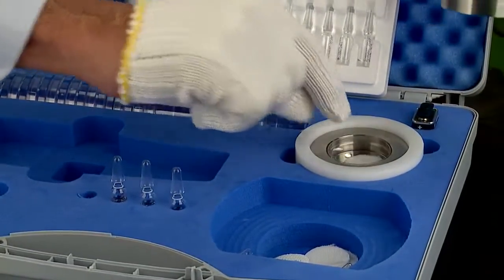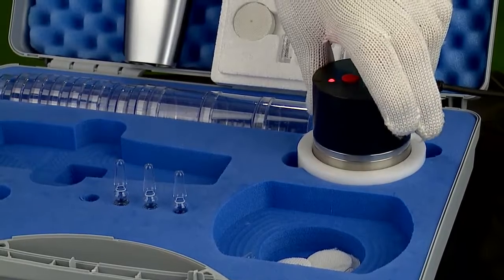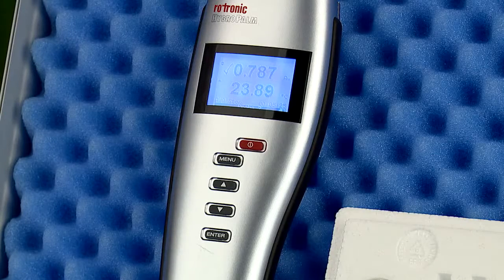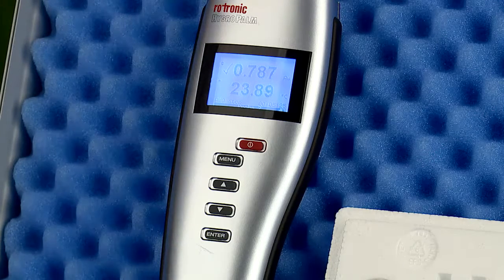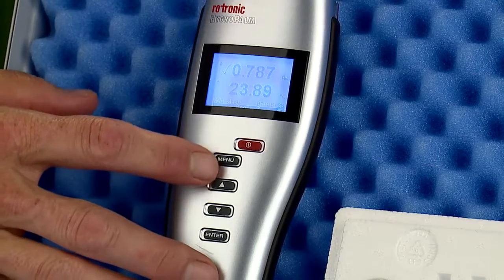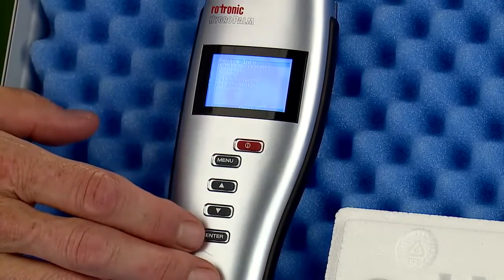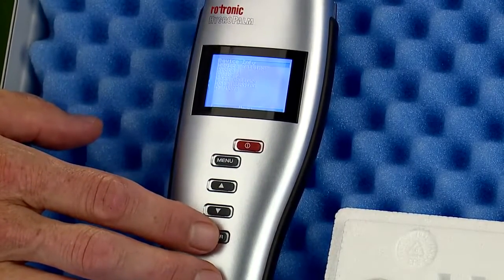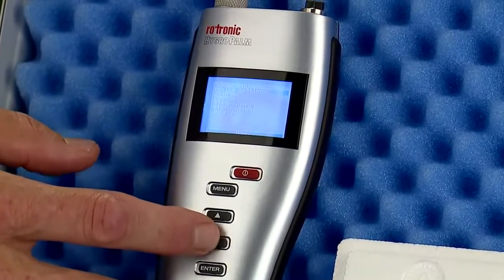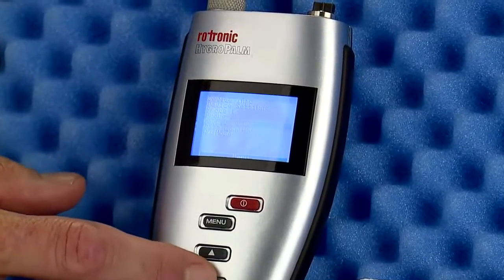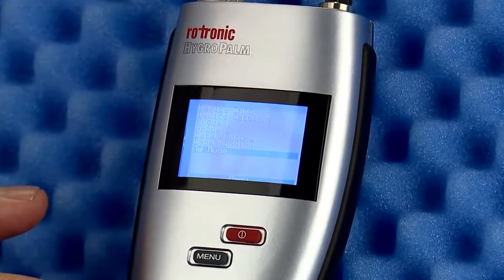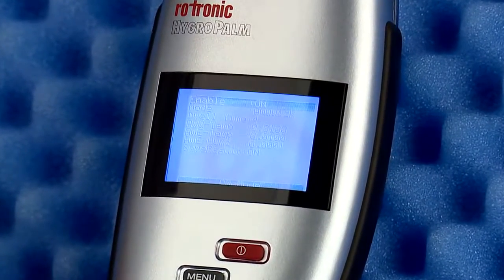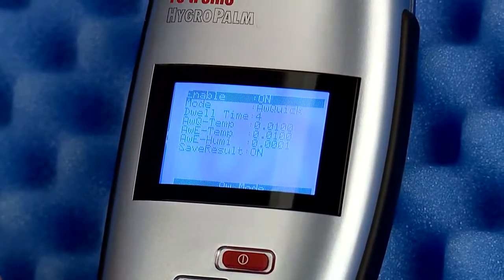While waiting, it is a good time to change the settings on the HP23 AW to ready the instrument for calibration. Using the HP23 AW instrument, press Menu, navigate to the AW Mode option on the first menu, press Enter, select Enable, and turn this selection to Off.